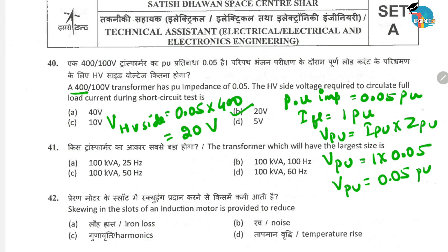Next is, the transformer which will have the largest size. According to the options, it is option A, because the lowest frequency will have the largest size of the transformer. Next is, skewing in the slots of an induction motor is provided to reduce? Skewing in the slots is always provided to reduce the harmonics. The correct option is option C.